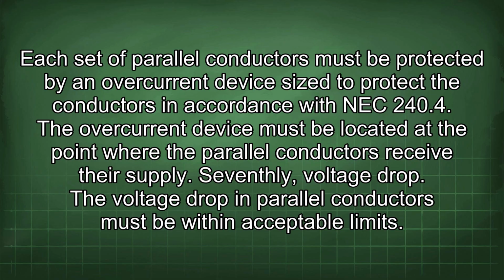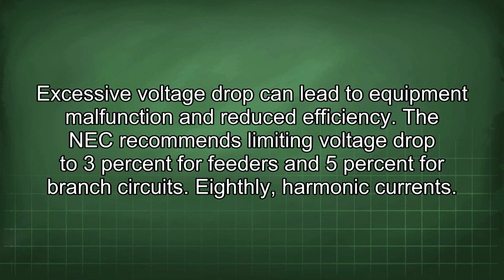The overcurrent device must be located at the point where the parallel conductors receive their supply. Seventhly, voltage drop. The voltage drop in parallel conductors must be within acceptable limits. Excessive voltage drop can lead to equipment malfunction and reduced efficiency. The NEC recommends limiting voltage drop to 3% for feeders and 5% for branch circuits.